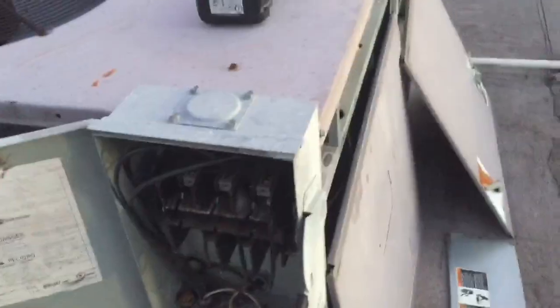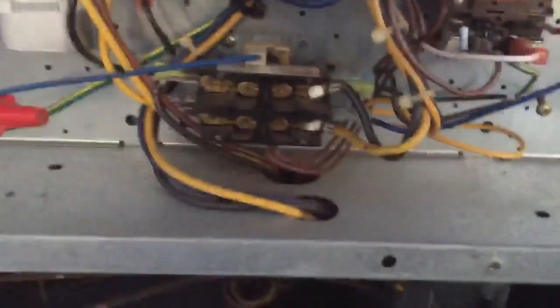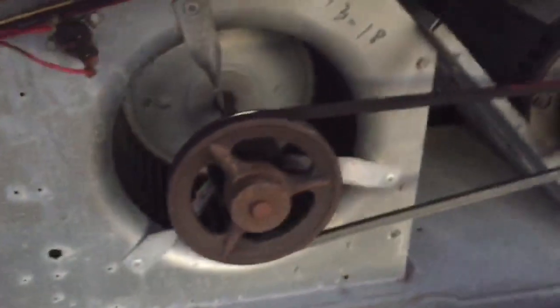Alright guys, it's the moment of truth. I did the repair, went to turn it back on. I can see the damages from earlier. I made the swap for the wires from blue to yellow, which is right on the top — yellow and blue. This one was rotating backwards, three phase. So switch some wires and you can rotate it the right way.